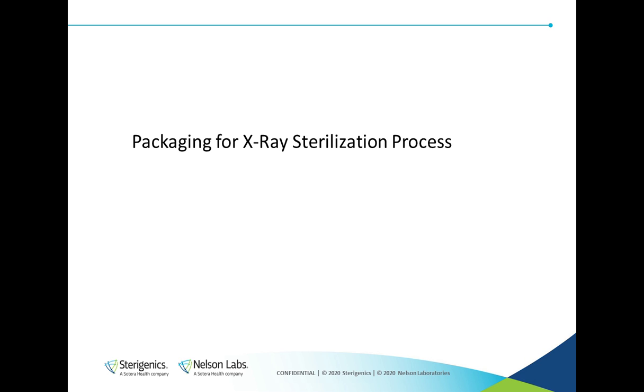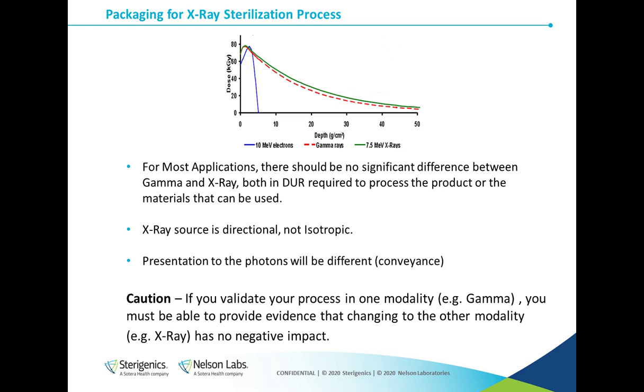Next, we're going to discuss really briefly the packaging considerations relative to the X-ray sterilization process. If you recall the depth dose curve that I presented earlier, the depth dose profile for X-rays is very similar to that for cobalt-60. The main difference between gamma radiation and X-rays is the source. In the case of gamma radiation, the photons are emitted by the radioisotope cobalt-60, and the source is isotropic, whereas X-rays are produced by a machine and are much more focused in a single direction.